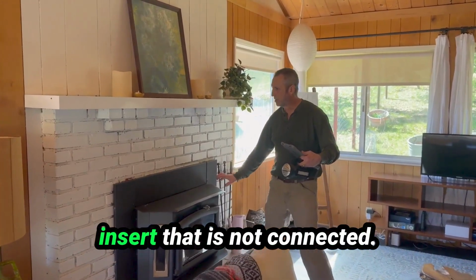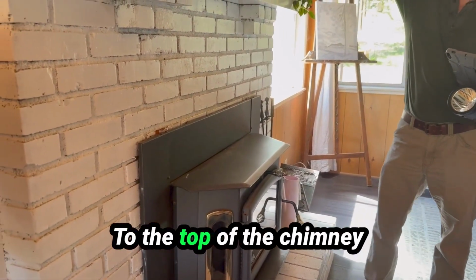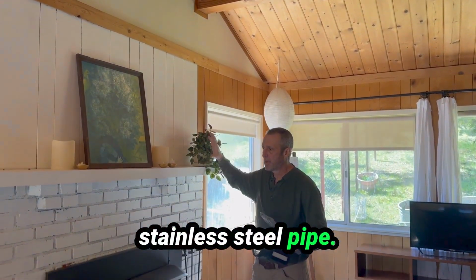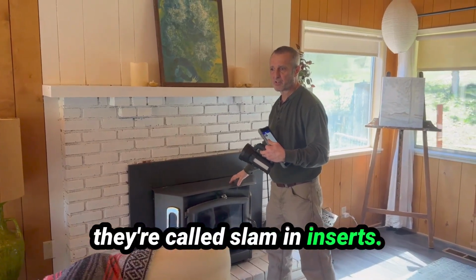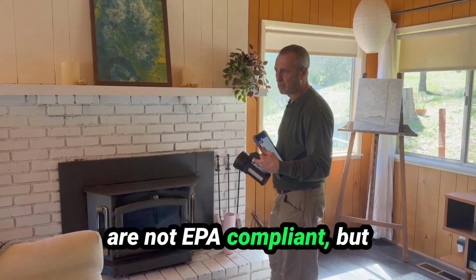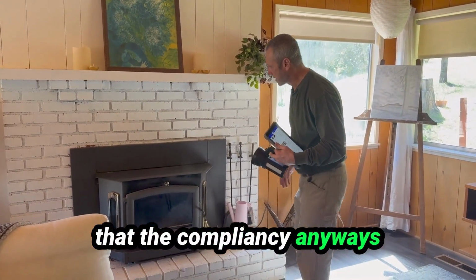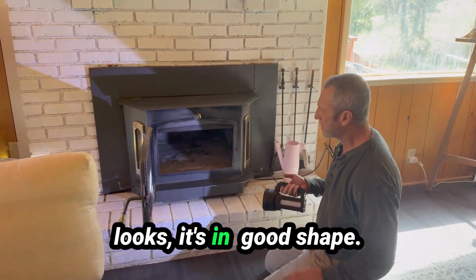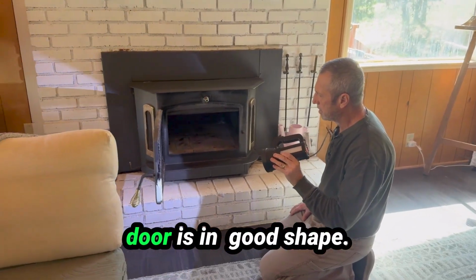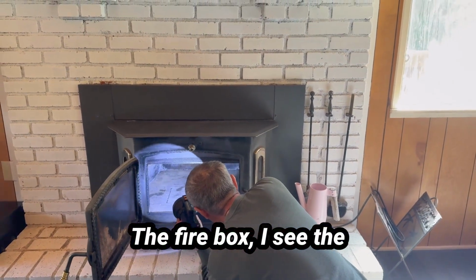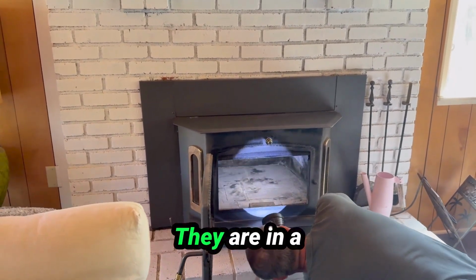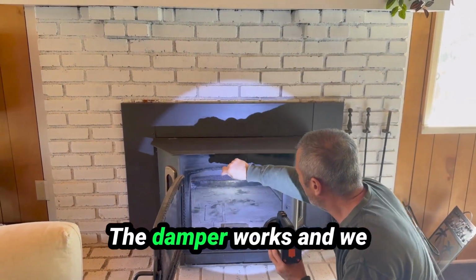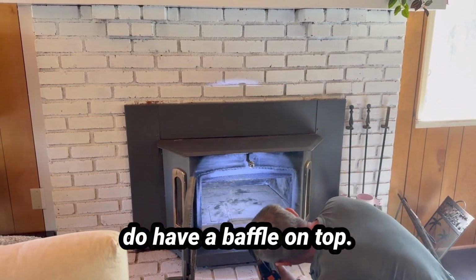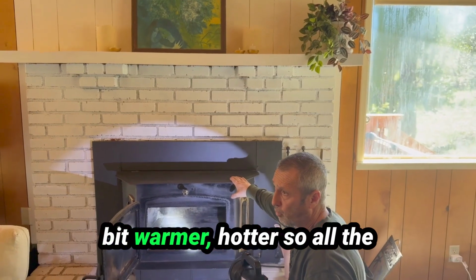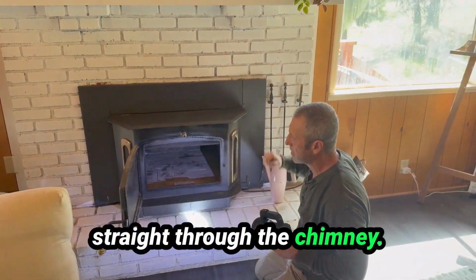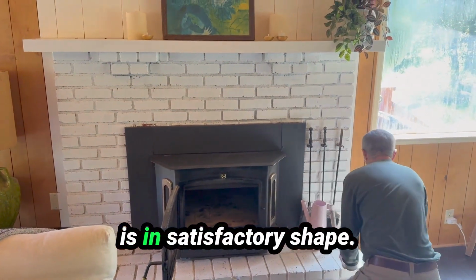Here we have a wood burning insert that is not connected to the top of the chimney with a 6-inch flexible stainless steel pipe. It's just slammed in, they're called slam-in inserts. Those kind of inserts are not EPA compliant, but this county doesn't ask for that compliance anyway. The insert from outside looks in good shape, the gasket on this door is in good shape. The firebox, metal firebox and bricks at the bottom, are in satisfactory condition. The damper works, and we have a baffle on top that helps keep this insert warmer, hotter, so the heat doesn't just escape straight through the chimney. So I'd say this insert is in satisfactory shape.